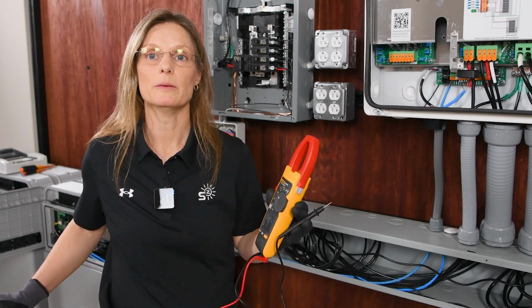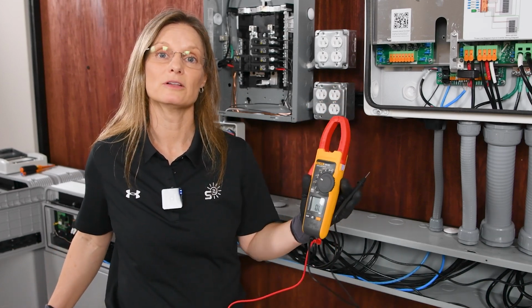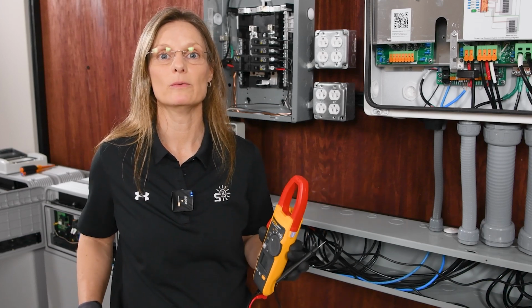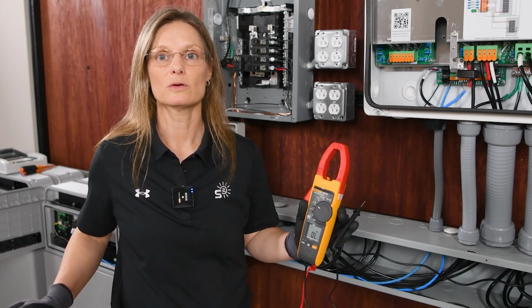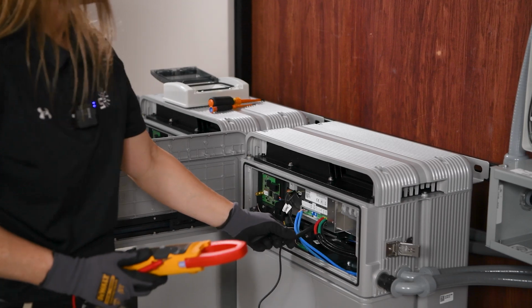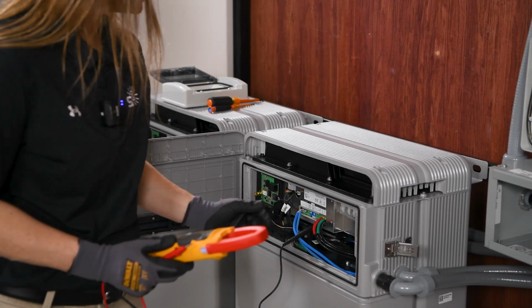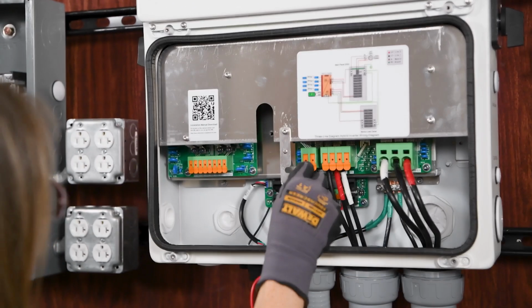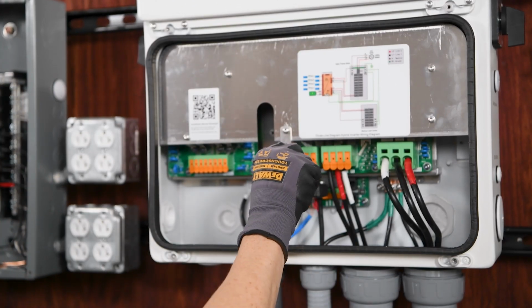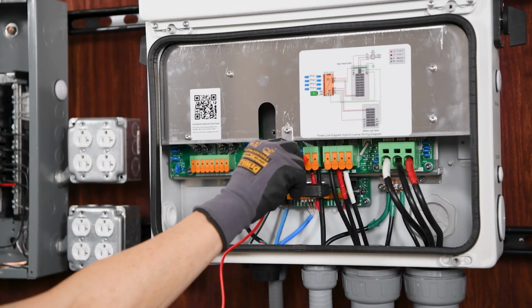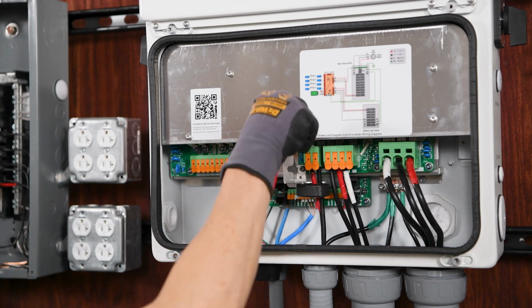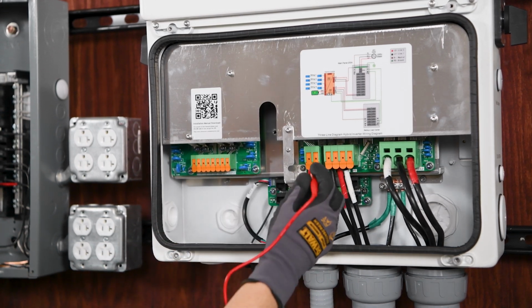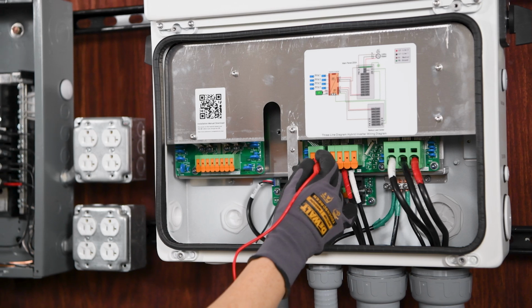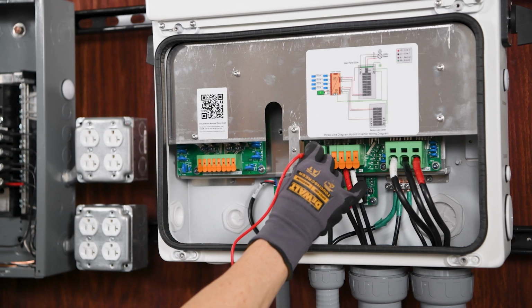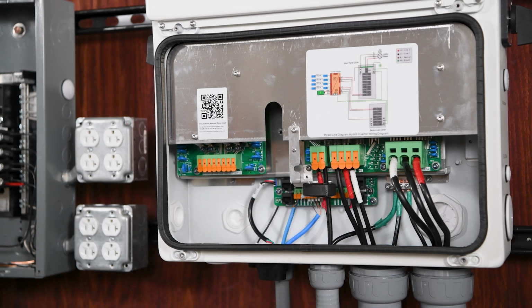When we put one probe into a positive and one into the negative, we are looking to make sure that we don't have a beep. That way we don't have any pathway for electrons to flow. So putting my black probe into the positive terminal and red probe into the positive terminal, we hear a beep, which means we have a good connection there. And we shouldn't hear a connection if we put it into the negative. So that is good. We have no cross polarity happening.